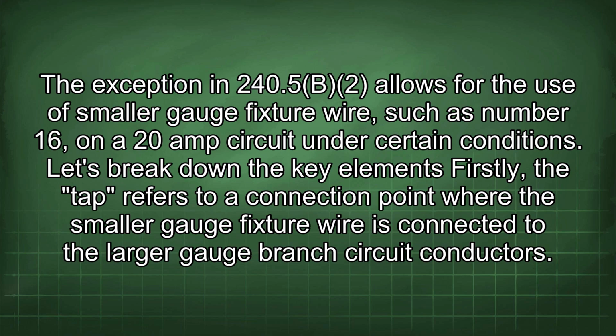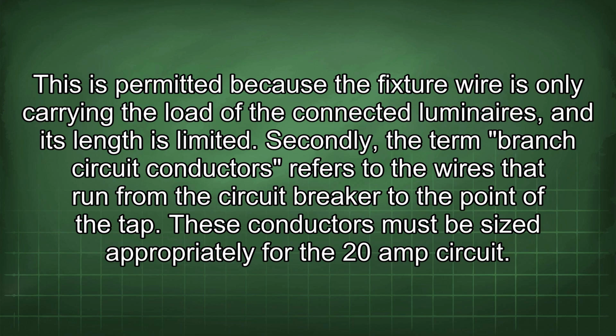The exception in 240.5(B)(2) allows for the use of smaller gauge fixture wire, such as number 16, on a 20-amp circuit under certain conditions. Let's break down the key elements. Firstly, the tap refers to a connection point where the smaller gauge fixture wire is connected to the larger gauge branch circuit conductors. This is permitted because the fixture wire is only carrying the load of the connected luminaires, and its length is limited. Secondly, the term branch circuit conductors refers to the wires that run from the circuit breaker to the point of the tap.